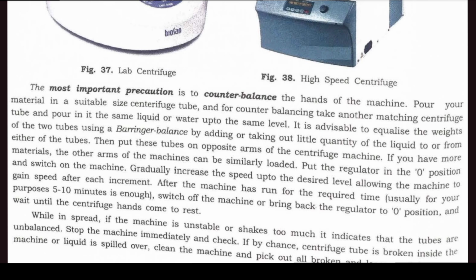Put the regulator in the zero position and switch on the machine. Gradually increase the speed up to the desired level, allowing the machine to gain speed after each increment. After the machine has run for the required time, usually for your purposes 5 to 10 minutes is enough, switch off the machine or bring back the regulator to zero position and wait until the centrifuge arms come to rest.